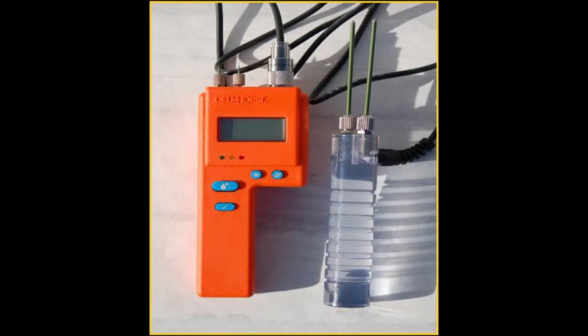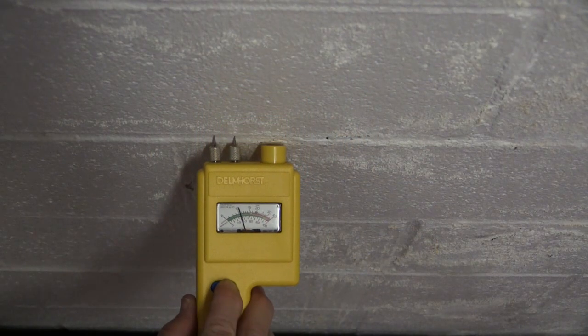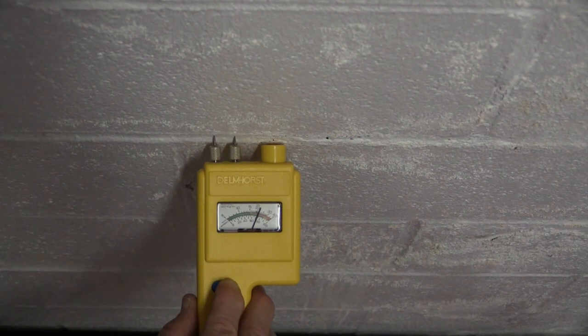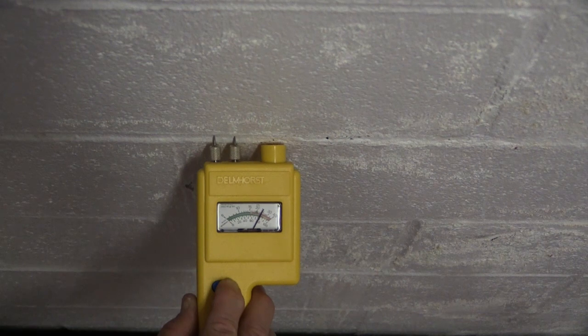The levels and descriptions are specific to this particular manufacturer and they aren't based on industry standards. A third moisture meter is based on electrical resistance or conductivity to determine the moisture content. Two contact pins on the end of the instrument are pushed against the test surface to measure the conductivity of the material between the pins. One manufacturer recommends driving masonry nails into the surface about a quarter inch in depth and touching the probe to the head of the nails.